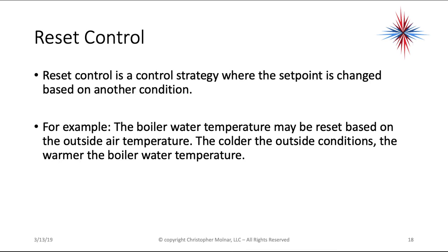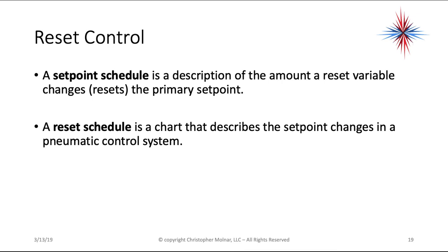Reset control is a control strategy where the set point is changed based on another condition. For example, boiler water temperature may be reset based on outdoor air temperature — the colder the outside, the warmer the boiler water. This can also be done with chilled water systems: if the temperature outside is cooler, less cold water is needed, saving energy. A reset schedule is a chart describing set point changes, commonly used in pneumatic (air-based) control systems.